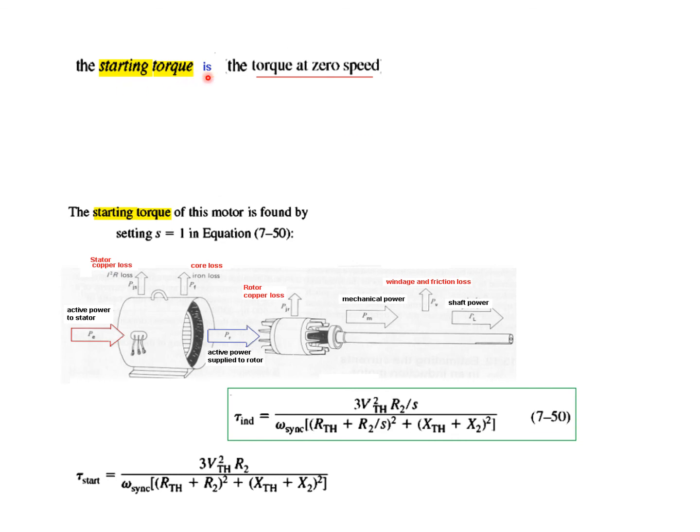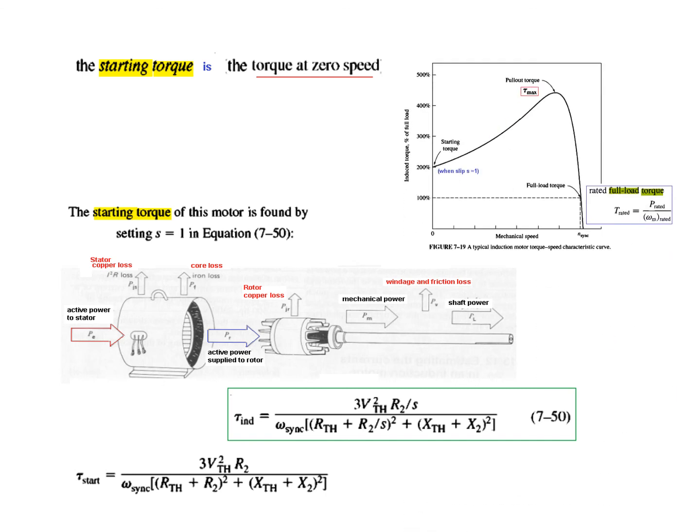And finally one more term left, that is the starting torque. The starting torque is the torque at zero speed here, speed is zero, rotor is standing still. So this torque is called the starting torque. We can find the starting torque by setting s equal to one. What does this mean? That the slip is hundred percent. Maximum slip is when the magnetic field is moving but the rotor is not moving. So there is maximum slip, and that is hundred percent or s equals one. So we put s equals one in the induced torque formula to get starting torque. So I hope this gives you an understanding of how you can derive all the relevant equations for the induction motor. Thank you.